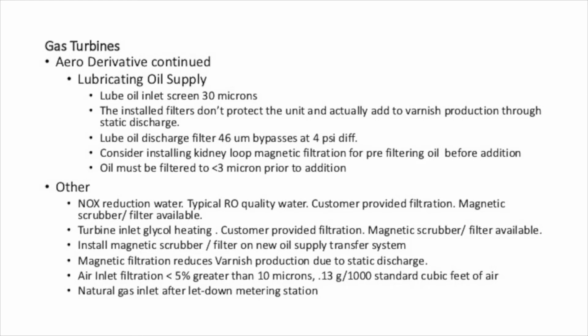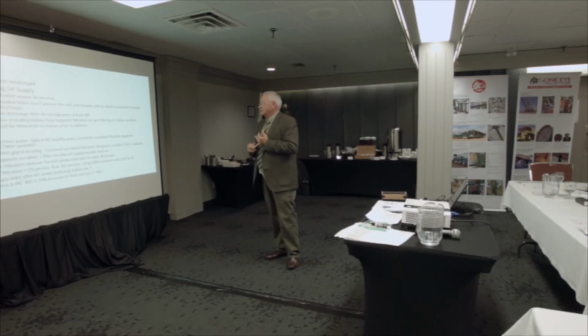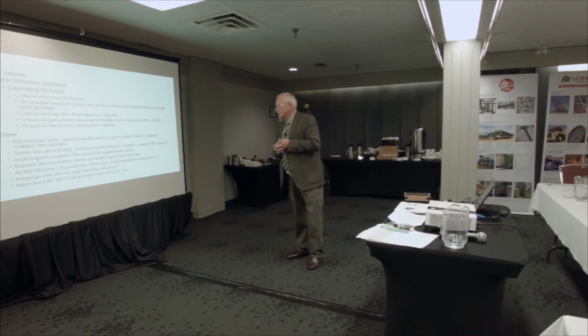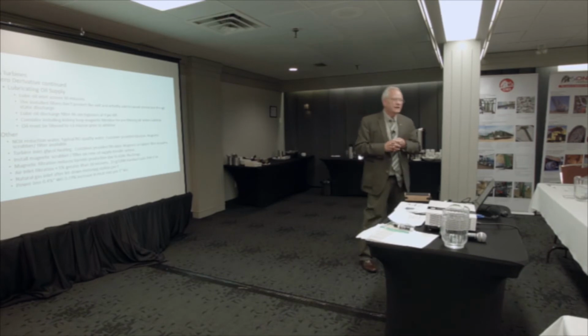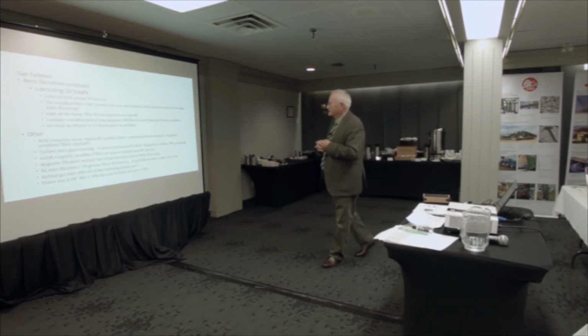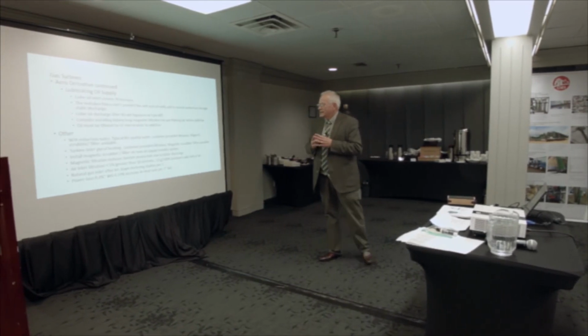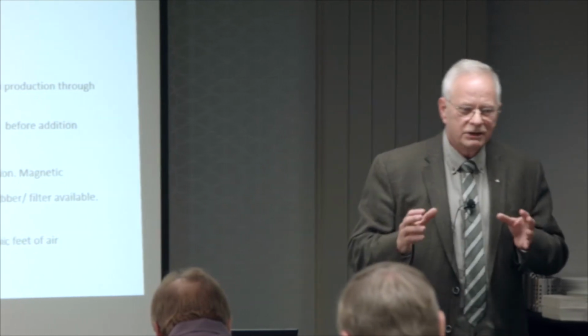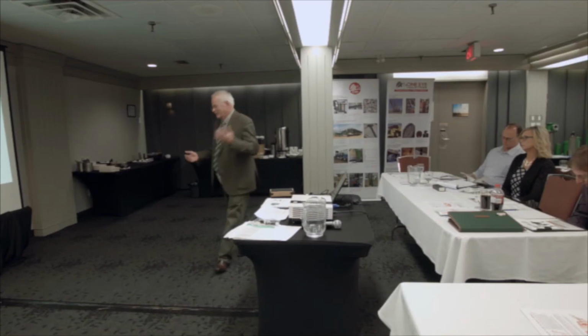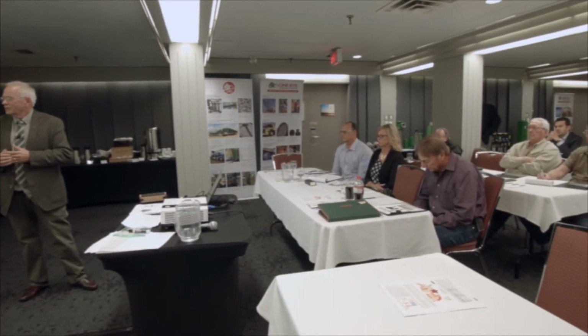So my recommendation is you have to provide a lot better secondary filtration for your gas turbines. A lot of the failures we've had on the gas turbines have to do with seals, loss of seals, and that's particle. A lot of it's particle size. To add to that, now they've added sprint units and they've added NOx or water injection for NOx reduction. You've got to make sure you filter that water supply, because when you're ingesting 500 cubic feet a second of air with water sprayed in there, anything that comes into the water or that's collected in the air is going right into your turbine.